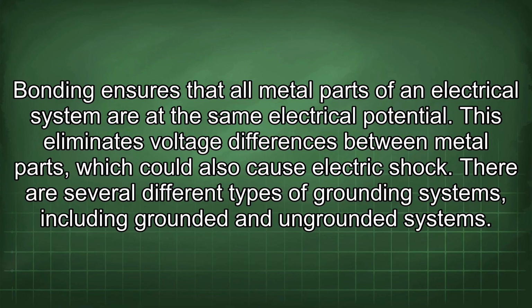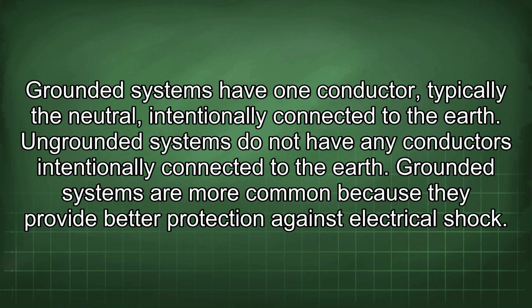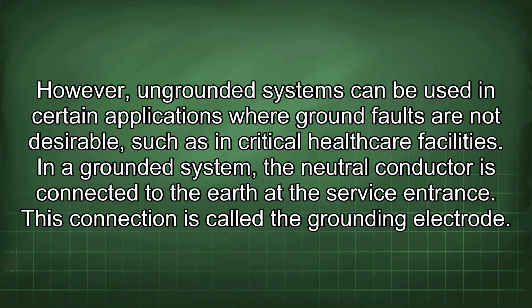There are several different types of grounding systems, including grounded and ungrounded systems. Grounded systems have one conductor, typically the neutral, intentionally connected to the earth. Ungrounded systems do not have any conductors intentionally connected to the earth. Grounded systems are more common because they provide better protection against electrical shock. However, ungrounded systems can be used in certain applications where ground faults are not desirable, such as in critical healthcare facilities. In a grounded system, the neutral conductor is connected to the earth at the service entrance.